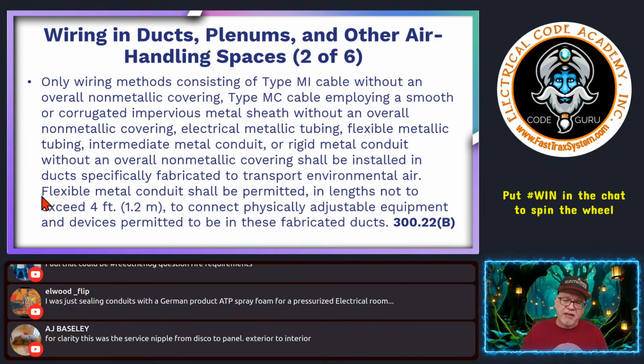You also can have FMC permitted in lengths not exceeding 4 feet to connect physically adjacent equipment, like those air sensing devices that are permitted to be in the actual duct. So while you have all these other methods that you could penetrate this environmental system, this duct system, if it's FMC, for example, you're going to be very limited in what you can penetrate. Okay? It's just to get to the sensor and get out, that type of thing. But these other methods can run in there further.